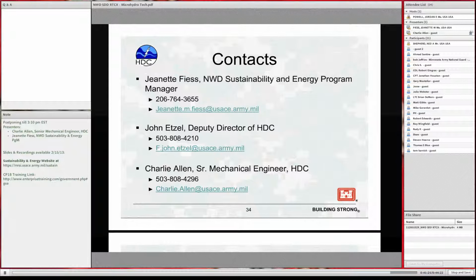This is Charlie. That's an excellent question. The classical large hydro answer to that question is approximately a 70% exceedance value. In other words, you will be spilling about 30% of your water because the turbines aren't big enough to handle that. For a micro or smaller hydro installation, I think we'd really want to look at it again on an individual basis. I would certainly not size it any smaller than 50%.